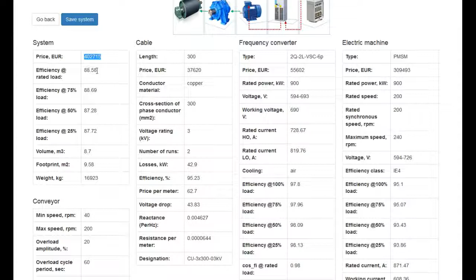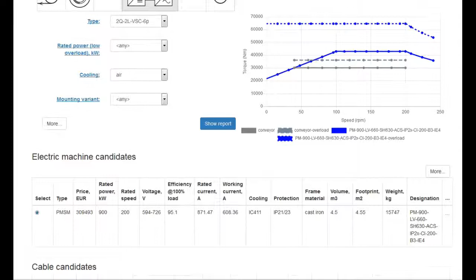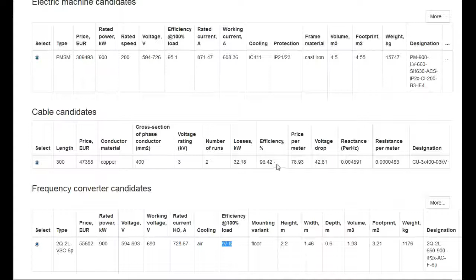It is 400,000 in price for the total system, and this is the efficiency at rated load. 88% is not too high. Well, now if we bring the cable cross section to 400 square millimeters, we can see some improvement in the cable efficiency. It's 96% now. The price is also 47,000. It is high. Now let's try the system with the transformer.